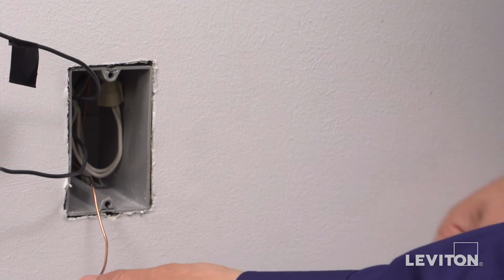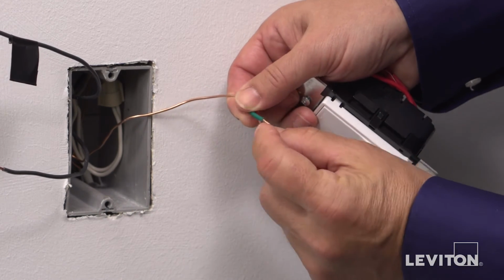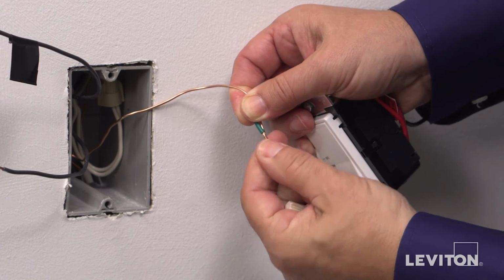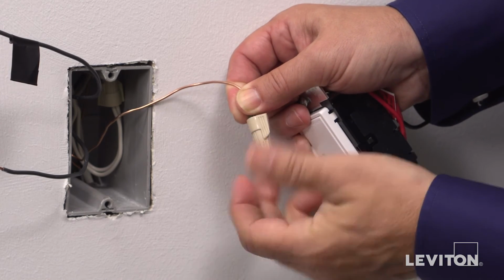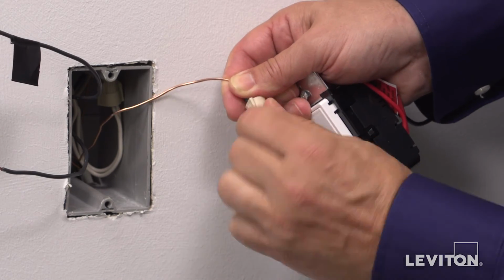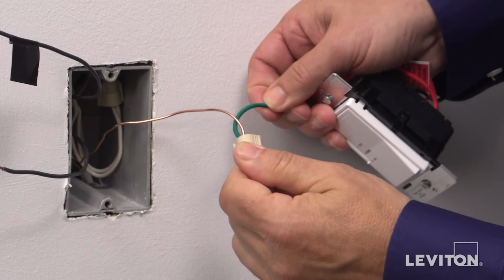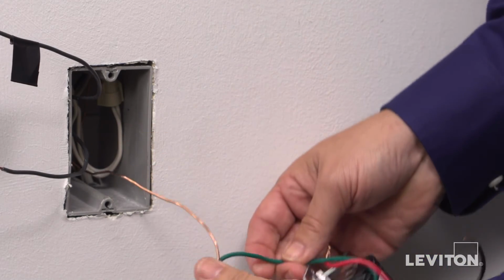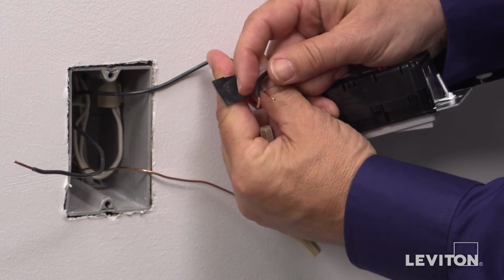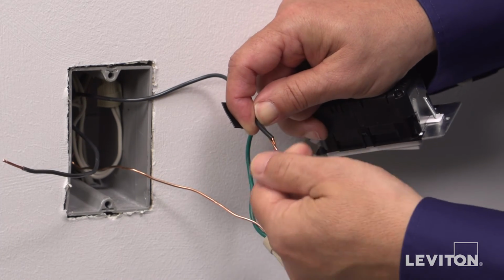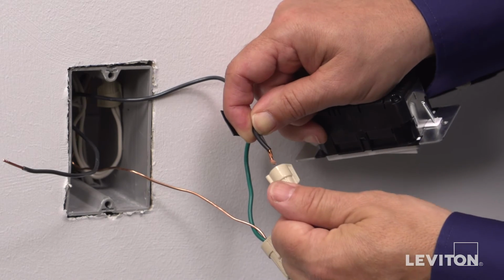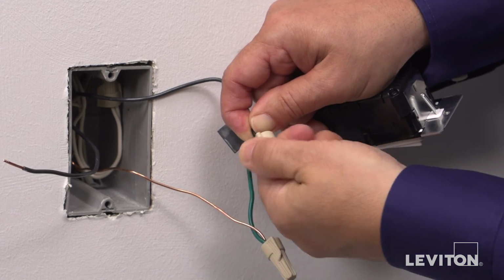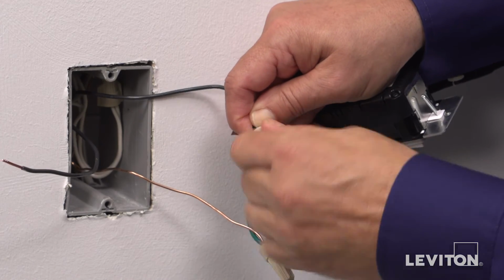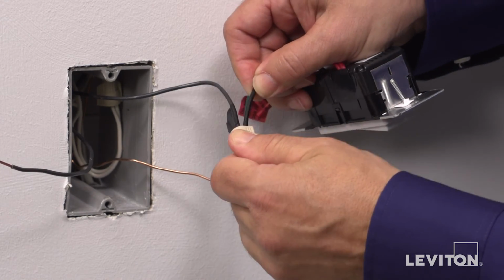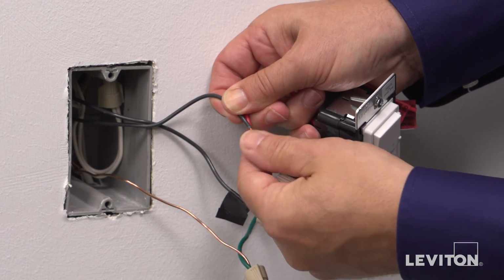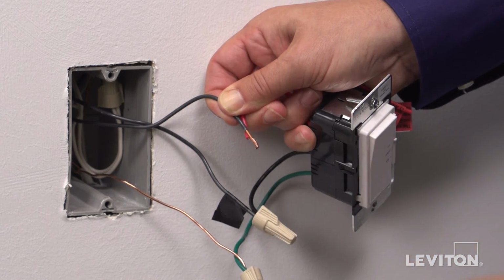To wire, take the green ground lead on the device and the ground wall box wire and twist in a clockwise direction. Insert them into a properly sized wire connector and twist the connector until the conductors bottom out inside and can't be twisted further. Next, wire together the black lead on the device and the black hot wall box wire. Finally, wire together the red lead on the device and the black load wall box wire.